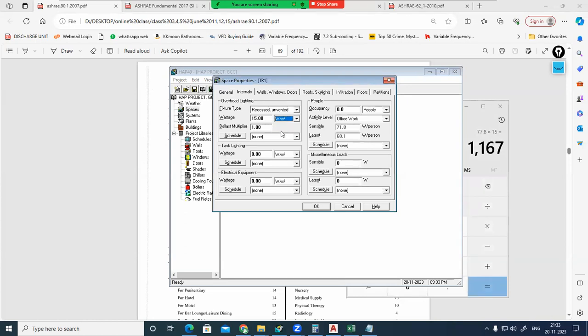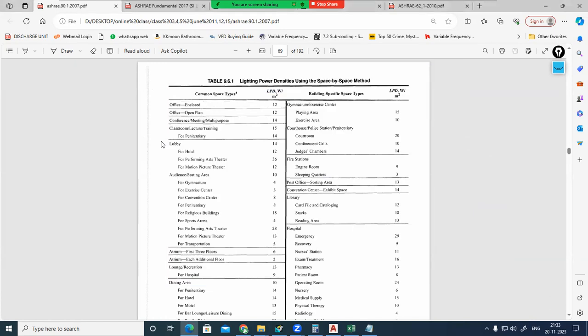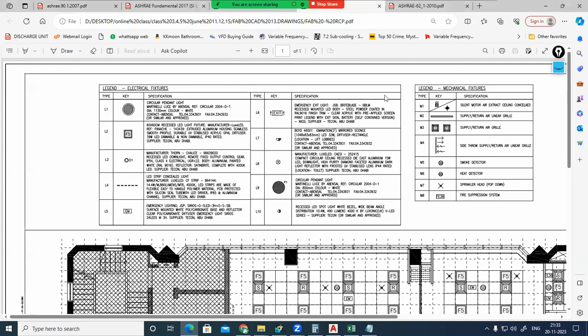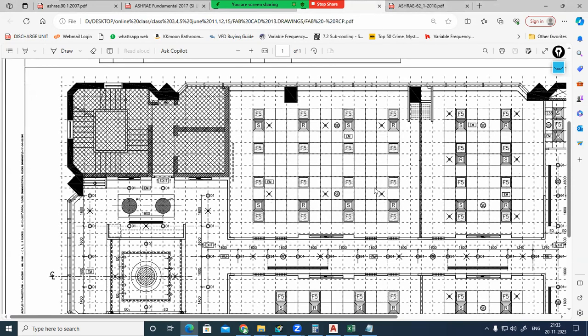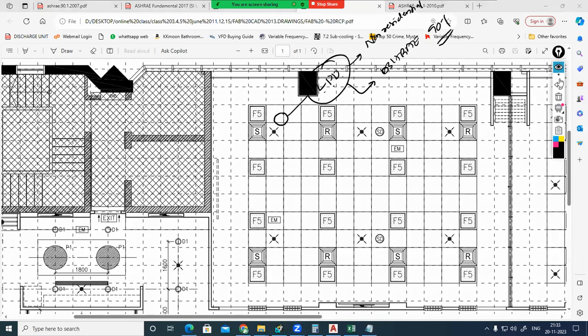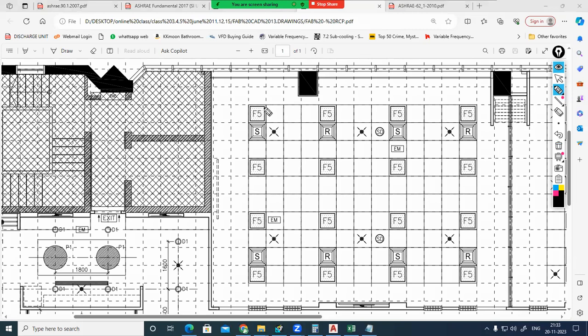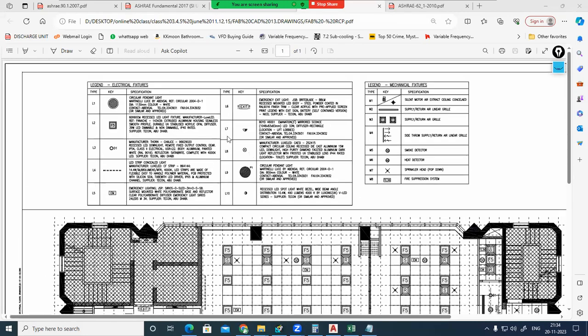Next, if you have light fitting details, definitely go for that. But that is very rare. If you have a reflected ceiling plan or a lighting layout, normally we will have lighting details in it. For example, in this PDF, the RCP, reflected ceiling plan of training room one. What is this F5? Normally you can study this in the upcoming sessions, this F5 is a light fitting only. This is SR, your air terminal, square diffusers only for HVAC. These are sprinklers, emergency lamp EM, SD like smoke detectors. But if you have doubt, you can go to the legend and find it there.